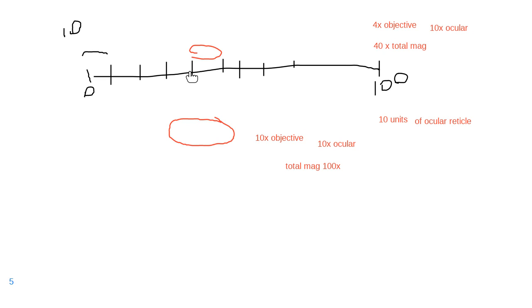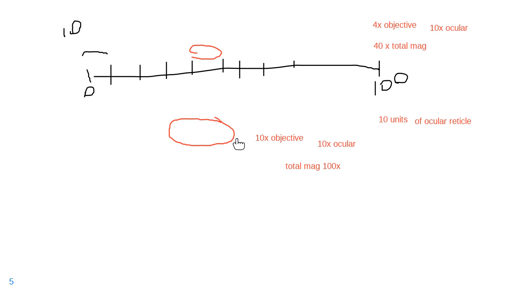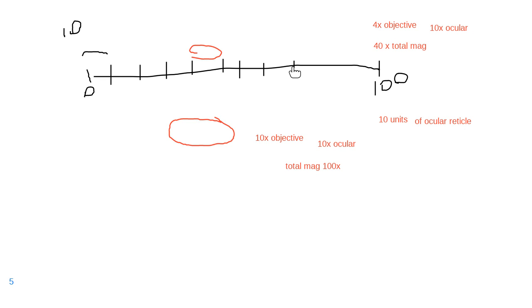But these spaces here, they cannot count the same number of micrometers. If you had assumed that this space meant 10 micrometers, now when I go to the next objective, my sample grows, but the detail is that my ocular reticle does not grow. That piece is not under the objective, it's in the eyepiece. So this line here stays the same size, and then your sample looks bigger.